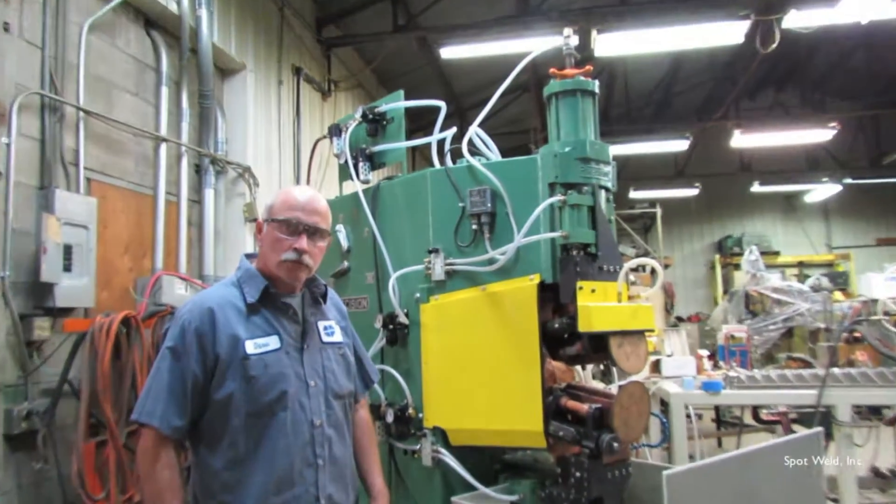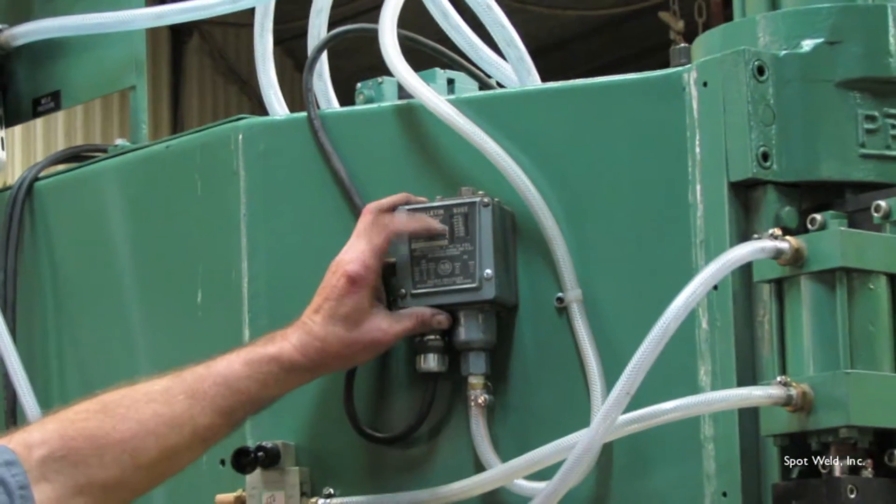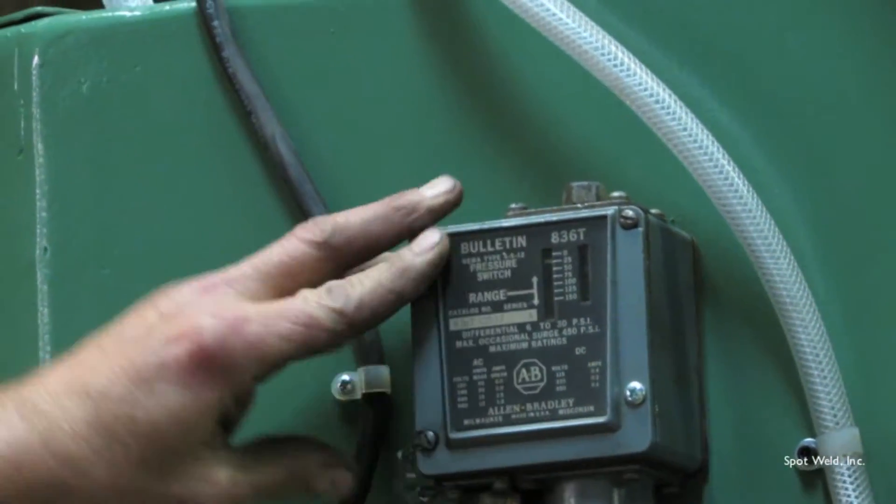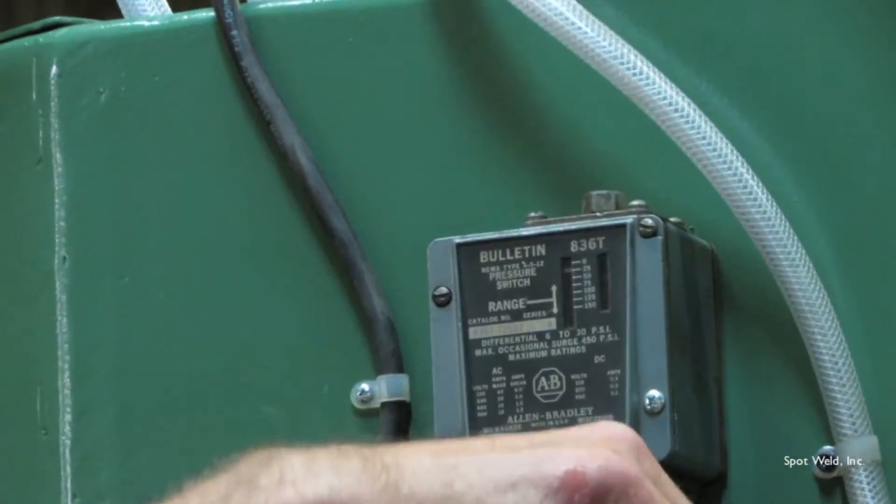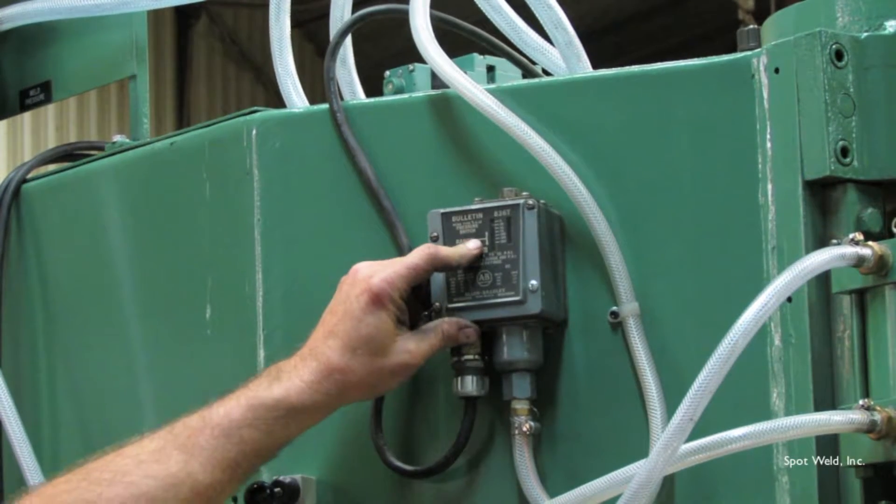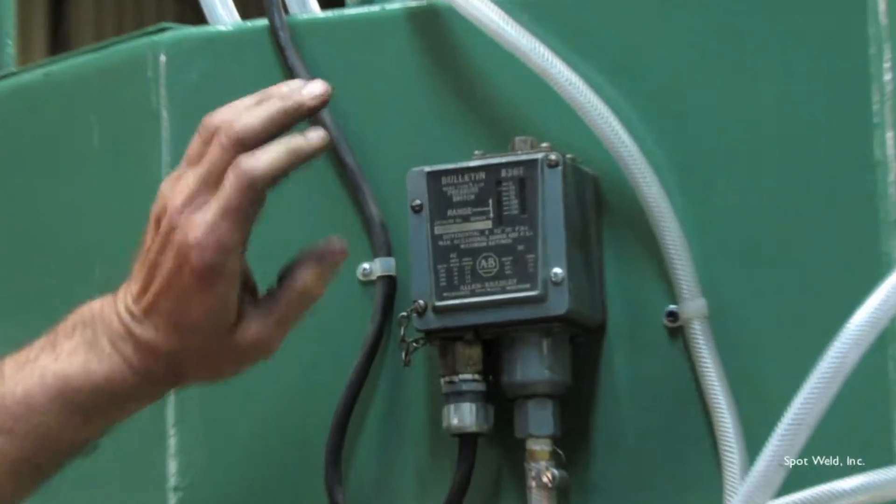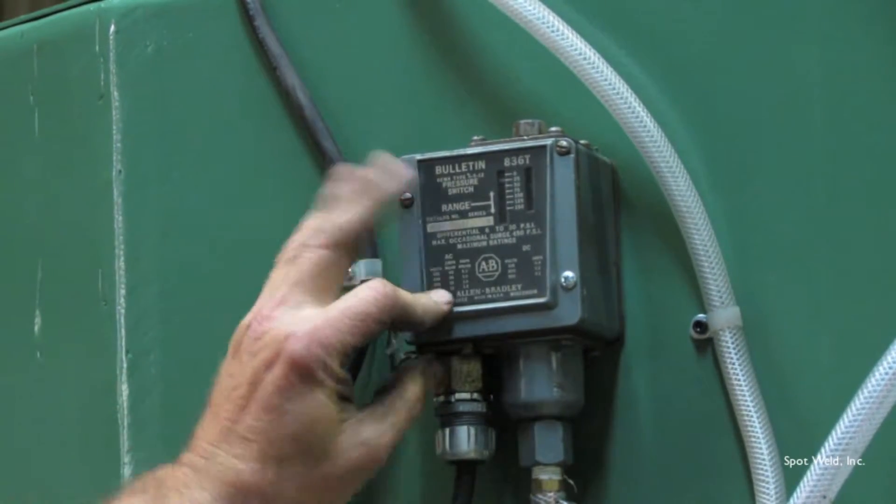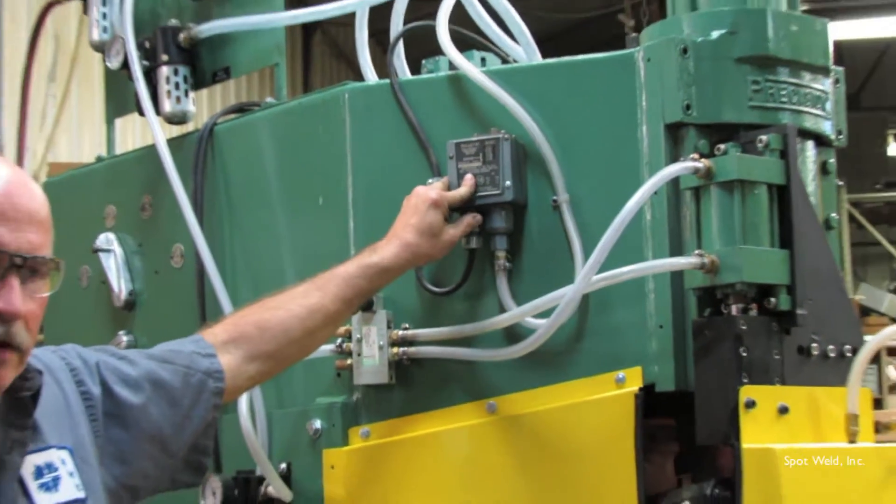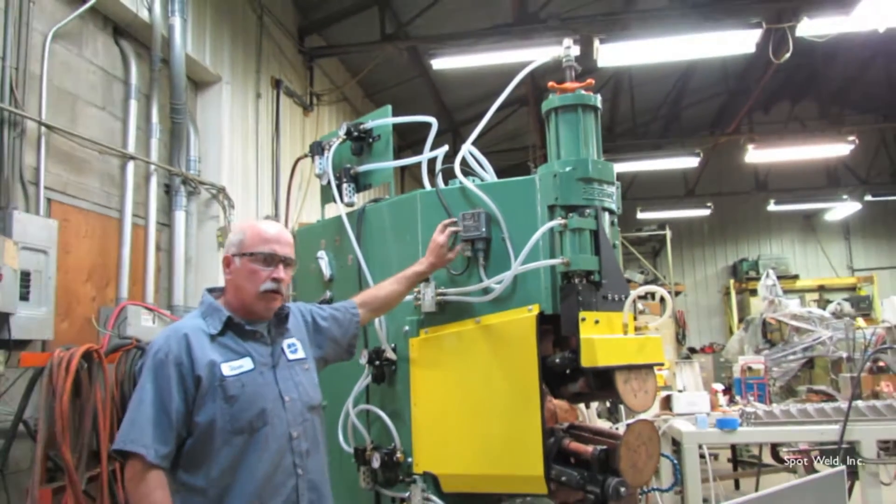You have a pressure switch here which is a must on a seam welder. The heads come together. When this makes pressure, it tells the welder okay, start welding and start the motor. That's your main safety on your wheels right there. If it doesn't have enough pressure, the wheels will sit there and wait. It won't weld until you get the right pressure.